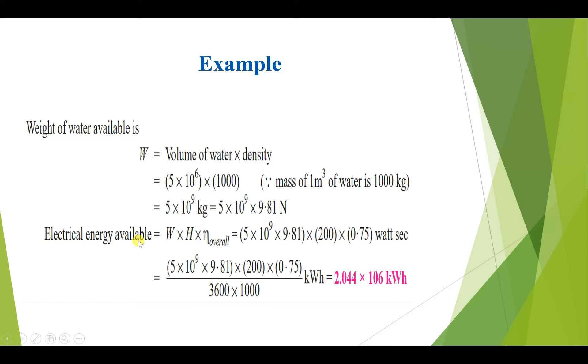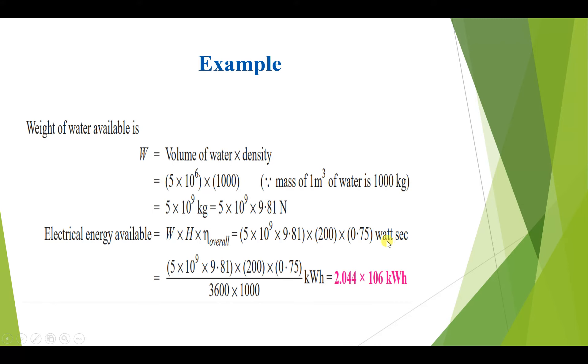The electrical energy available equals the weight of water W multiplied by the head and the overall efficiency. We have W = 5×10⁹ × 9.81 Newtons, the head is 200 meters, and the overall efficiency is 0.75 or 75%. This gives us the result in watt-seconds.